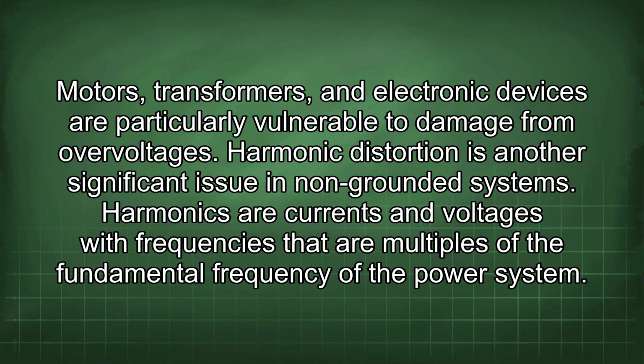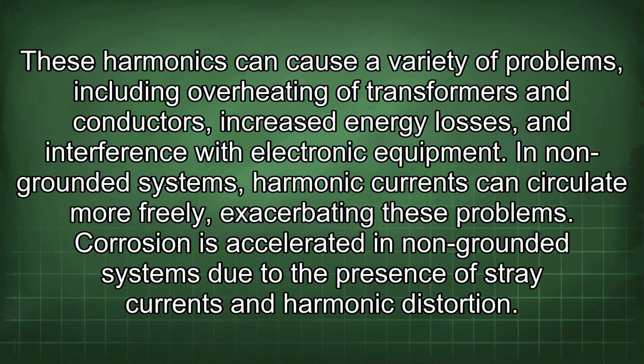Harmonic distortion is another significant issue in non-grounded systems. Harmonics are currents and voltages with frequencies that are multiples of the fundamental frequency of the power system. These harmonics can cause a variety of problems, including overheating of transformers and conductors, increased energy losses, and interference with electronic equipment. In non-grounded systems, harmonic currents can circulate more freely, exacerbating these problems.